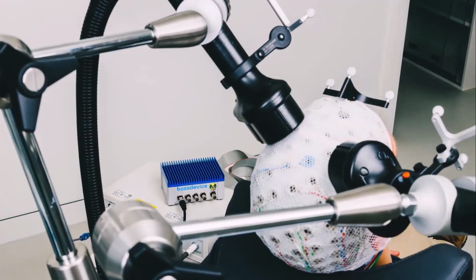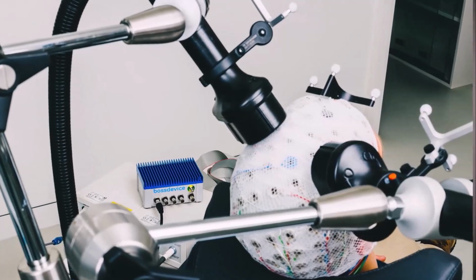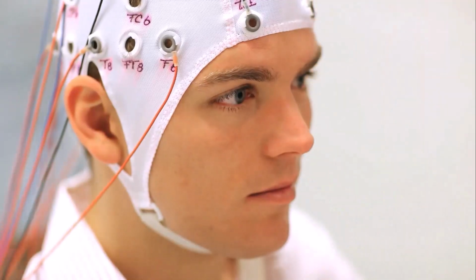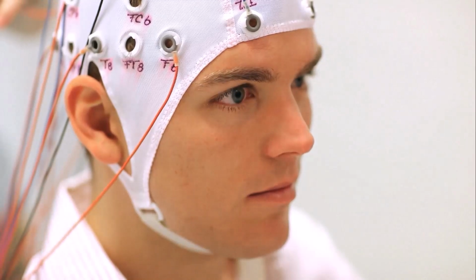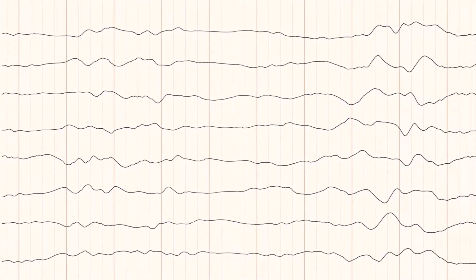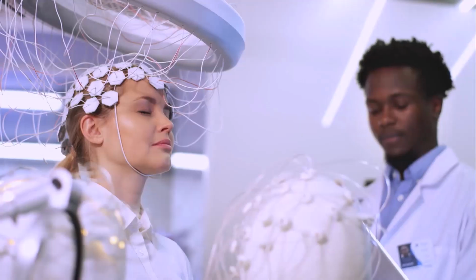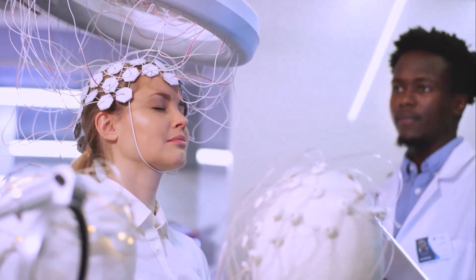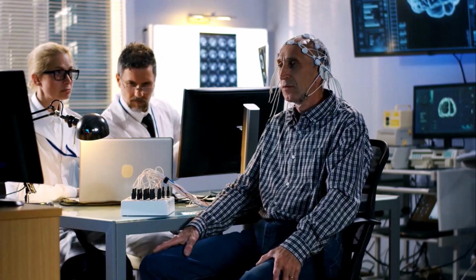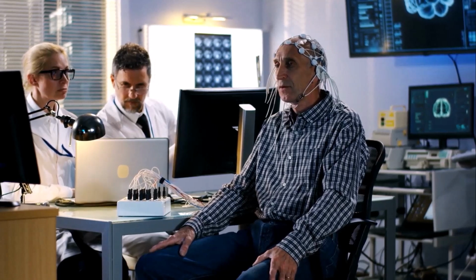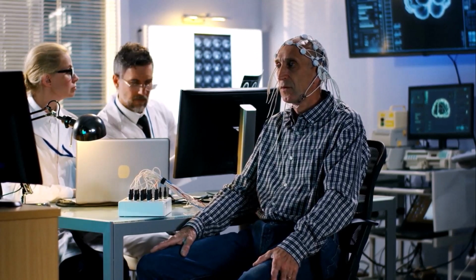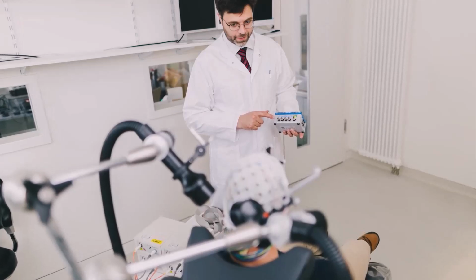The BOSS device is already available for researchers, but to be able to provide therapy to patients, we have to go through certification as a medical device. And this is what we have been focusing on. It involves a lot of testing, a lot of documentation to be compliant to all the different standards and norms. We have already reached some milestones for the hardware, for the company, with CE mark for Europe just within sight.